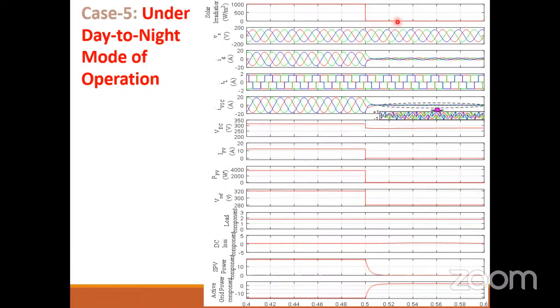And in the night time, when the solar irradiance is 0, you will see the PV power is 0. If the PV power is 0, then this VSC, voltage source converter, if you look at the waveform, this is the waveform. It means this voltage source converter is only generating nonlinear currents for this load. Since we have an accurate estimation, according to the estimated harmonic requirement of this highly harmonic load, the inverter is generating pure harmonic current, right? And then only the fundamental component comes from the grid. So you can see if you add this and this component, then this will generate. Like this way. So at night time, who is feeding this current?